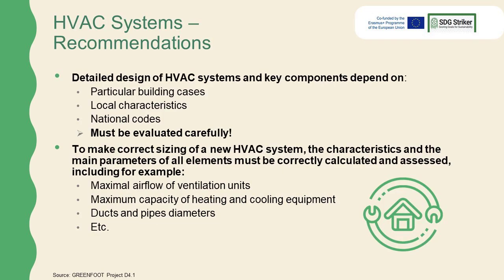Here are some recommendations for efficient heating, cooling, ventilation, and domestic hot water production. The detailed design of HVAC systems and key components depend on particular building cases, local characteristics, national codes. To make correct sizing of a new HVAC system, the characteristics and the main parameters of all elements must be correctly calculated and assessed, including, for example, maximal airflow of ventilation units, maximum capacity of heating and cooling equipment, ducts and pipes diameters, etc.